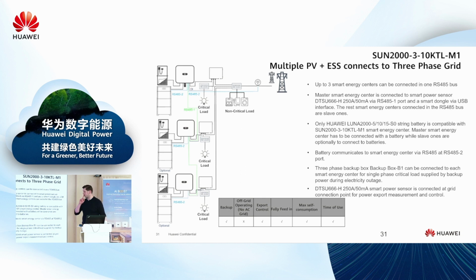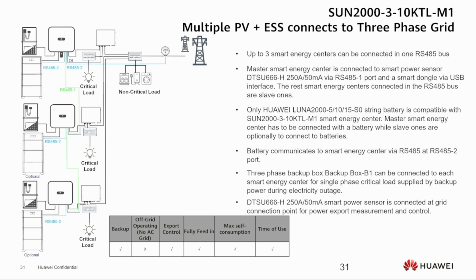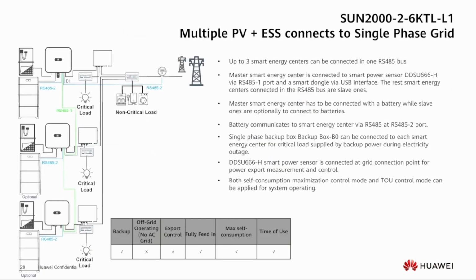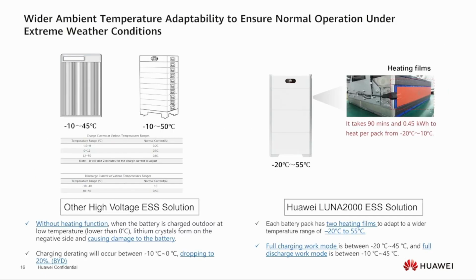The L1 series - I mean the single phase inverters - this is information I should have shared with you before: this is the inverter which supports a totally off-grid system. So you don't need the backup box, you don't need any other equipment, just inverter, PV modules and the battery, and you can have the fully off-grid mode. It's not switchable - when you choose the fully off-grid mode and the inverter detects voltage on the input, it will just trigger the alarm, like 'okay, I am in off-grid mode, there shouldn't be voltage here, so I'm shutting down.' But unfortunately, only single phase supports this scenario.